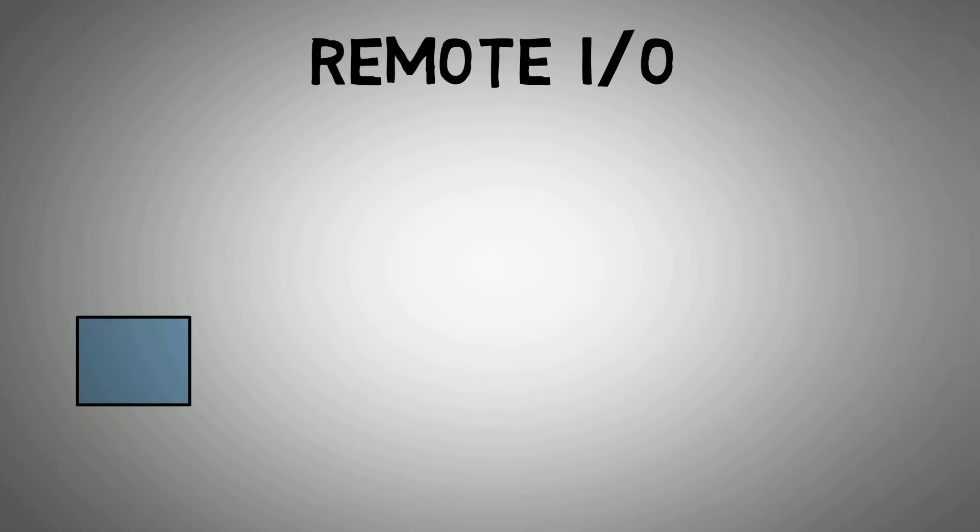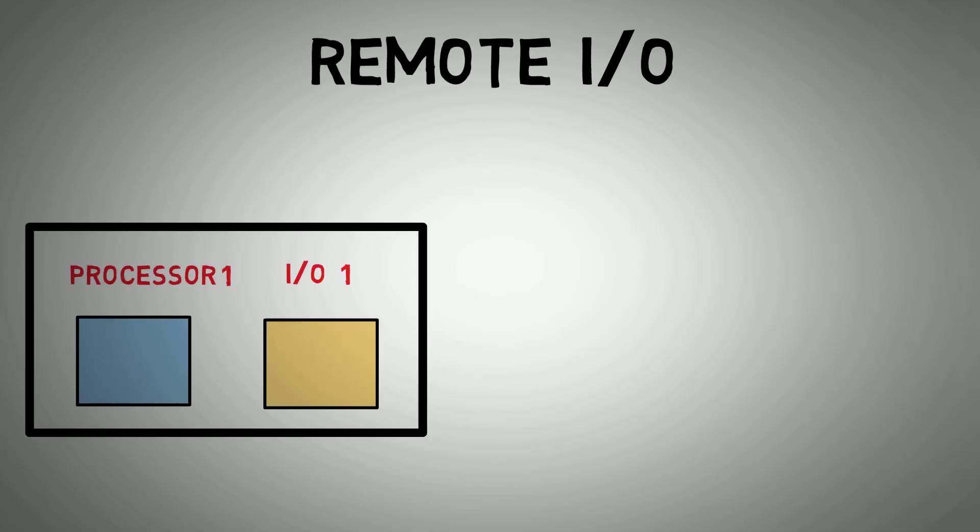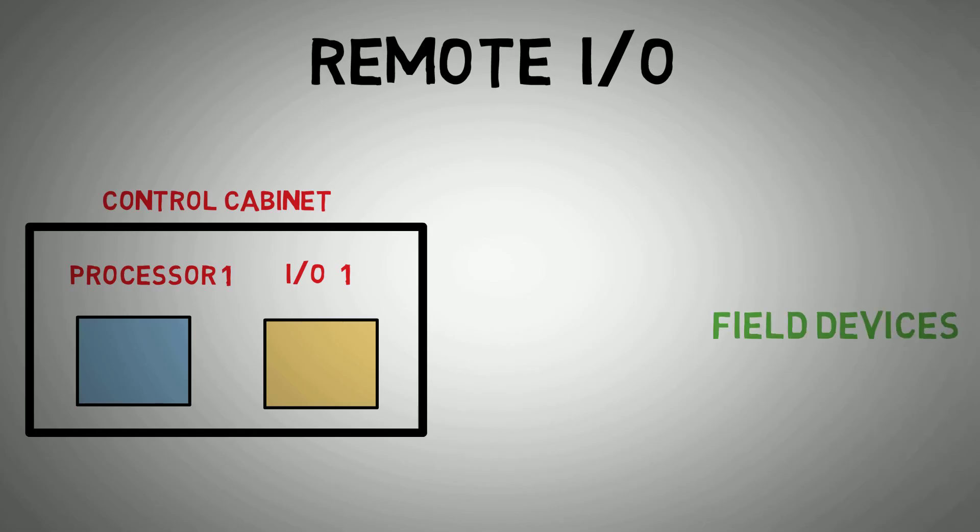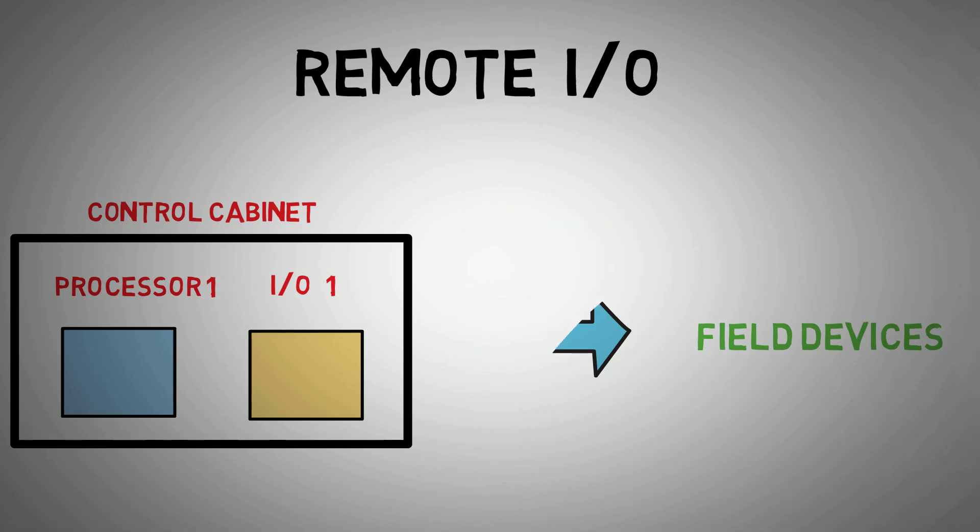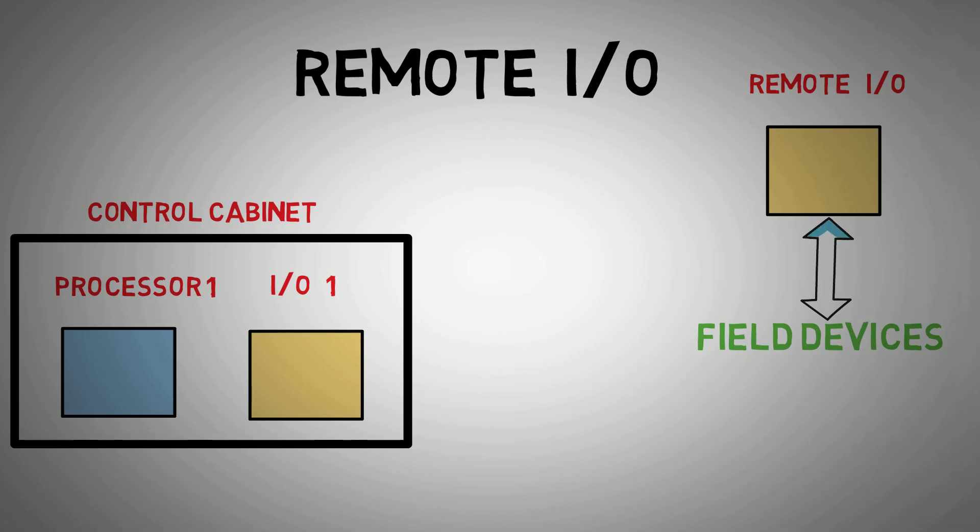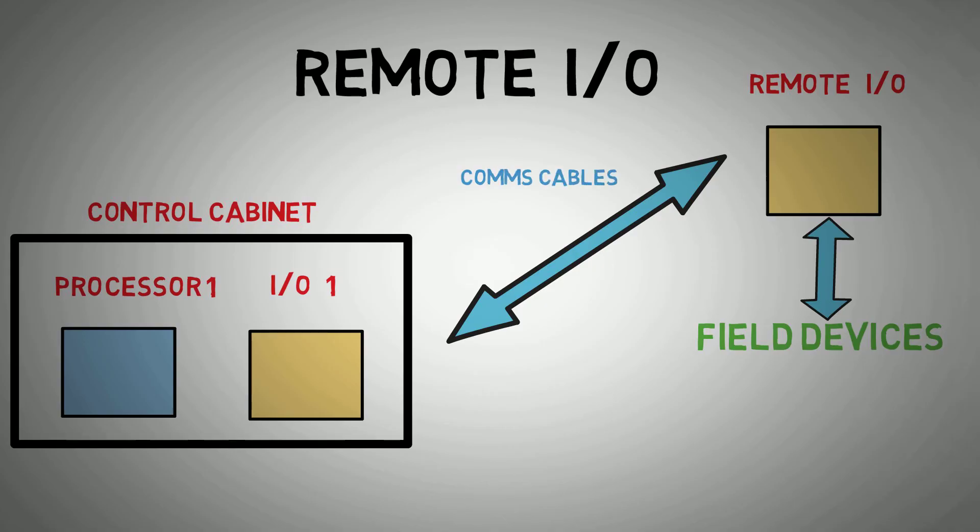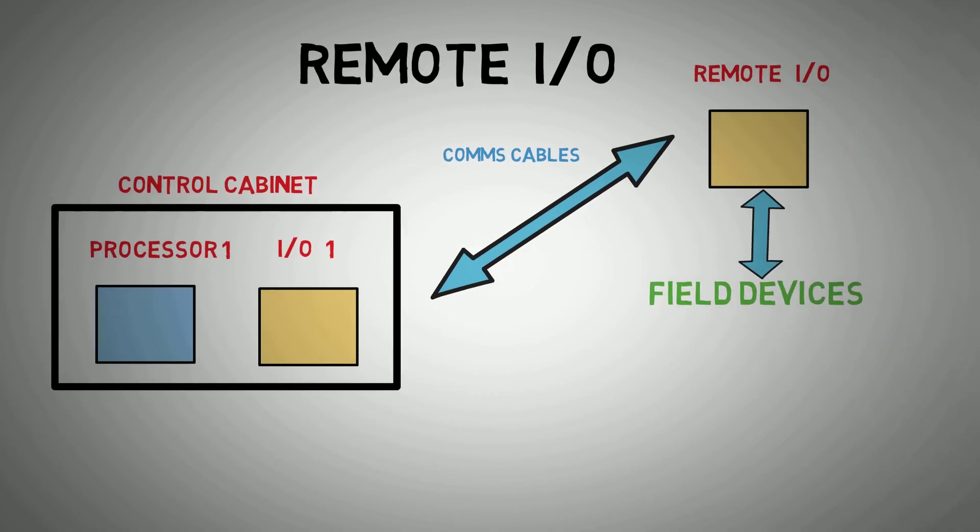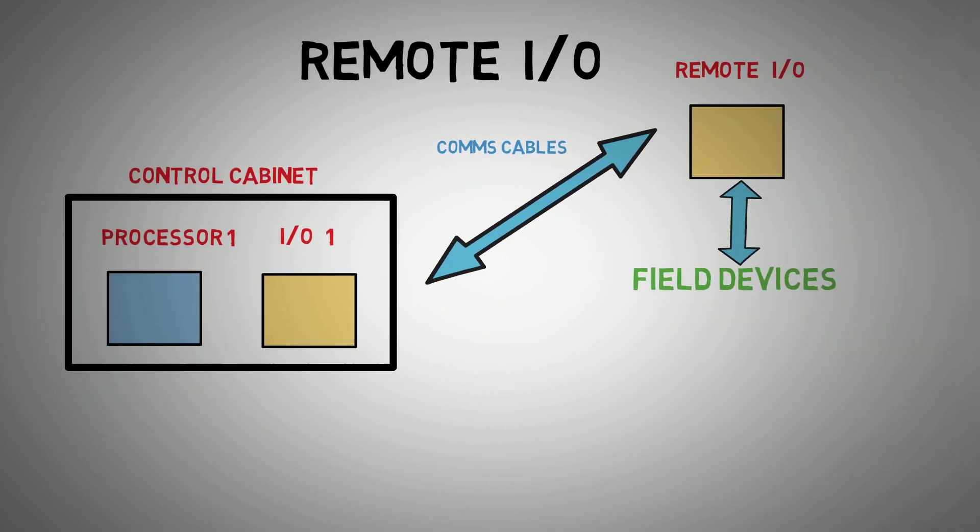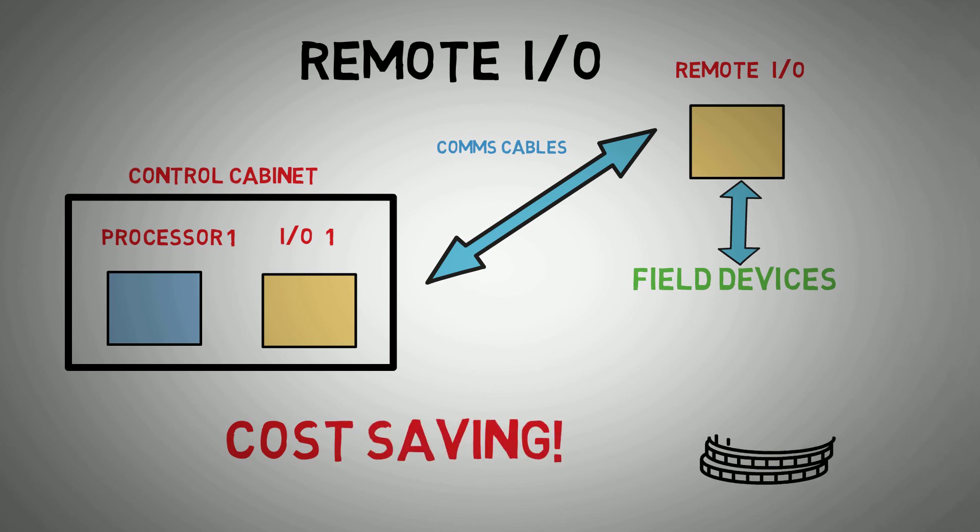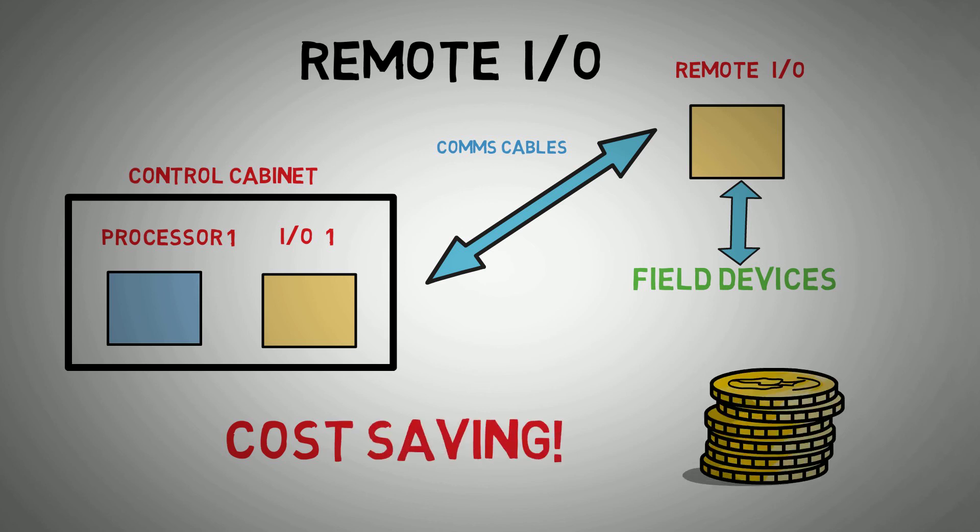It's worth mentioning here about remote I.O. infrastructure. In a standard I.O. configuration, we need to bring all our field device wiring back to a single point where the I.O. cards and processors are located. With remote I.O., we can have a set amount of I.O. in the field connected via short cable runs to field equipment within a specific area. We can then run comms cable from the remote I.O. to the main processor to carry that information. This vastly saves on the cost of multi-core cabling that might be needed in a standard setup.